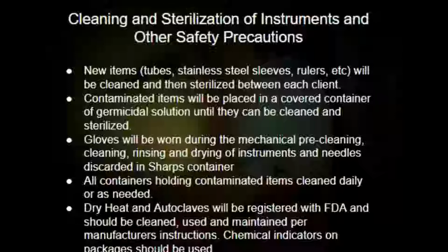Care should be taken to ensure removal of any pigment inside tubes not visible to the eye, then they are placed in a holding container filled with low-residue detergent in cool water. Instruments should be submerged into the soaking solution to keep any remaining organic matter from hardening, while instruments accumulate during pre-cleaning for the next procedure.